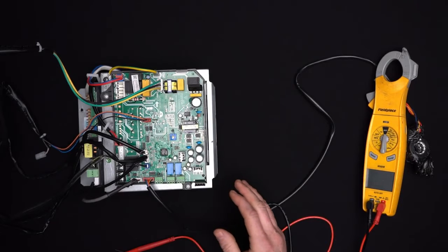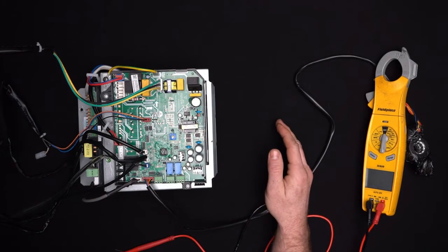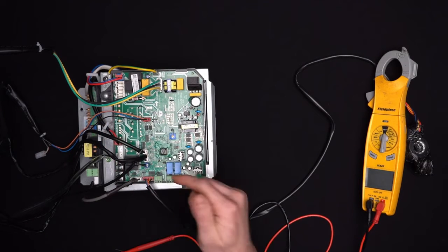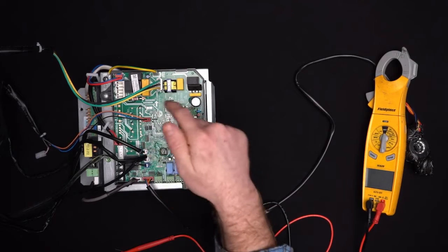So once the board has power, you've verified that there's power coming into the unit, you should verify that the power is going into the board. Once you have power going into the board, then you know that you should be getting power to your relays.